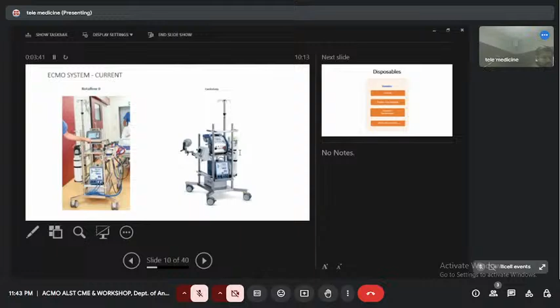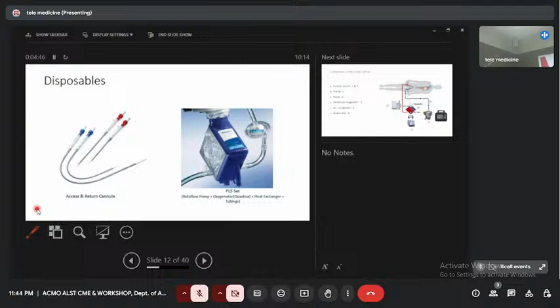So then comes the disposables that you have to manage with the patient. The cannulas, and of course the Rotaflow, the disposable pump, the oxygenator with the heat exchanger inbuilt, and the tubings with the connectors. So these, the smaller ones, the red ones, are your return cannulas. They return the oxygenated blood to the patient. The larger ones, blue ones, are your drainage cannulas. They drain the blood. This is your PLS set, okay? That has the oxygenator and heat exchanger fibers built in. From here, the connections for your water to heat up the blood as per your requirements, and the gas blender, and this is your pump.